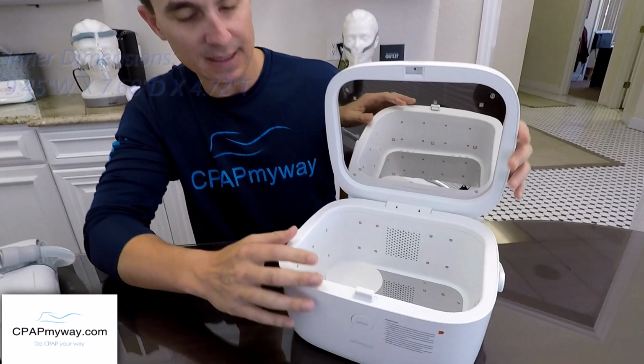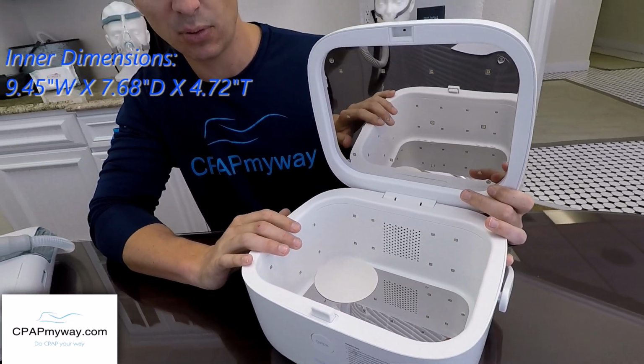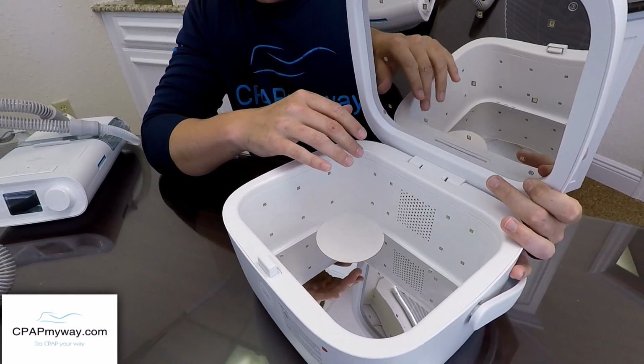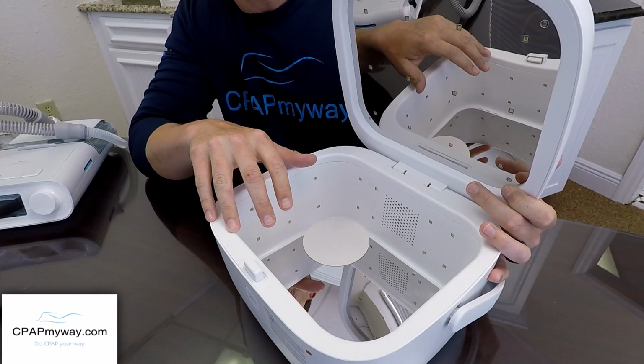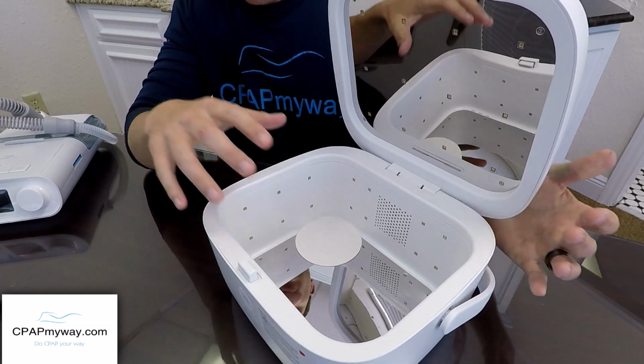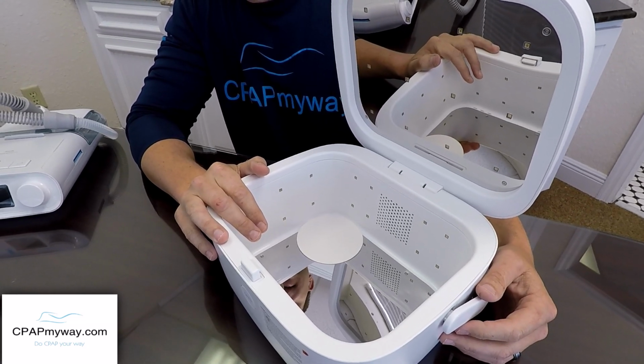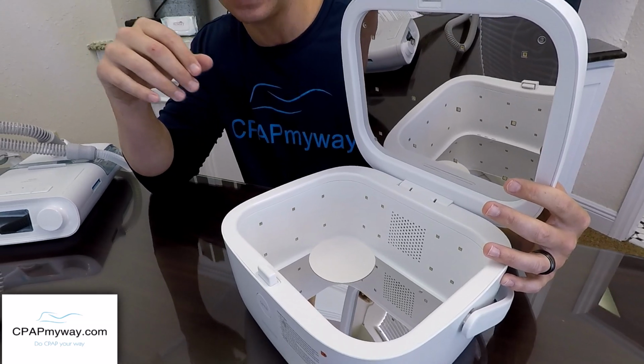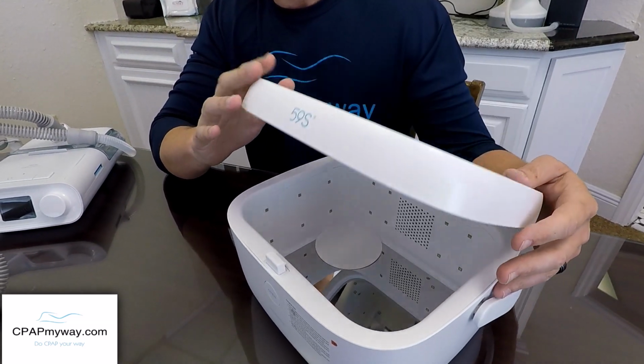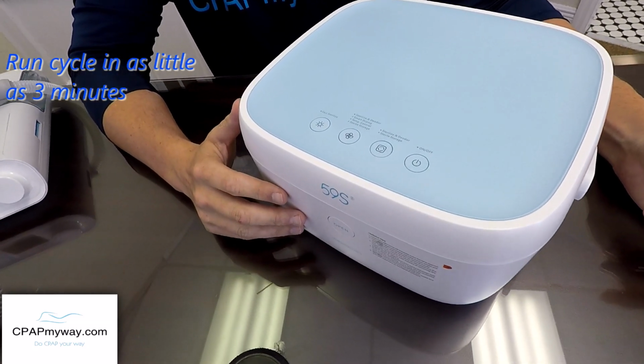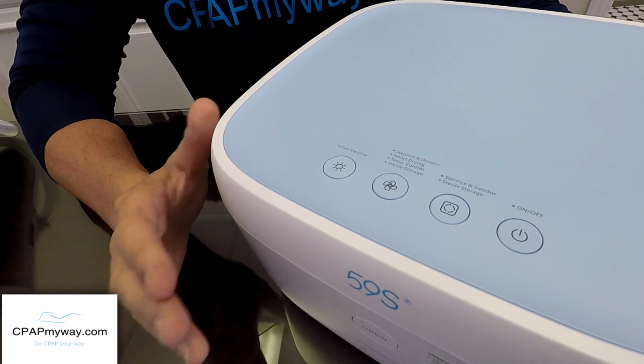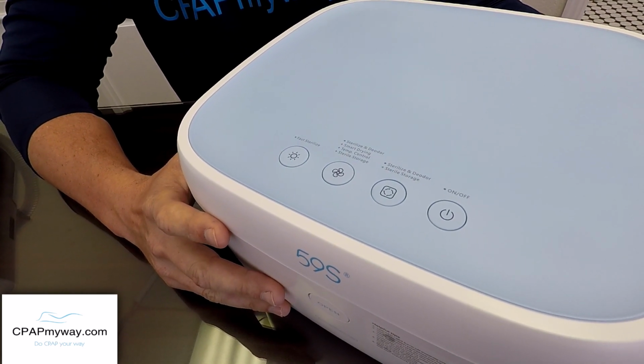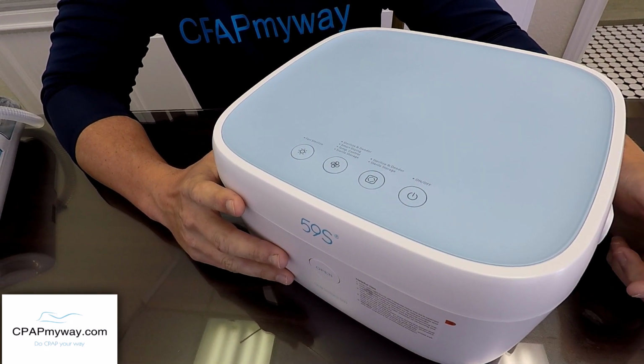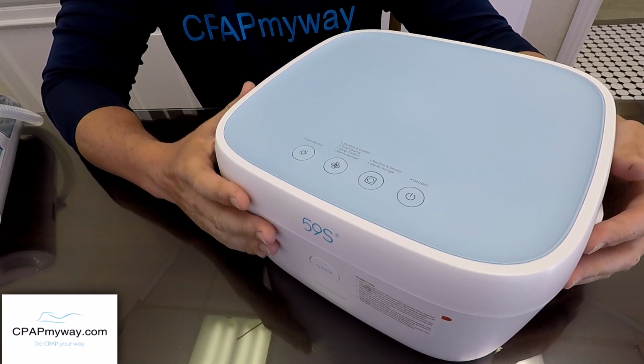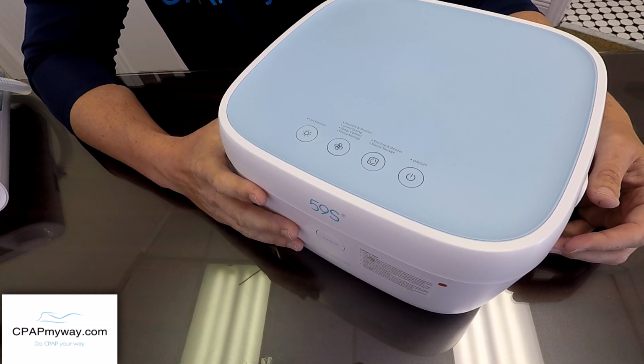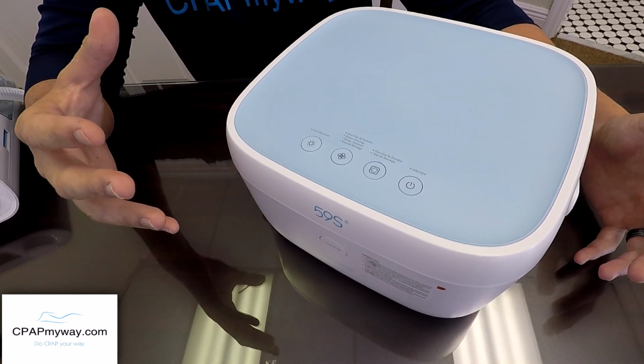Inside the device itself is the largest UV capacity, so it's 9.45 inches by about 7.68 inches, by 4.72 inches deep. So it holds quite a bit, and it definitely is something you'll want to consider because this has some options as far as what you'll be putting in there. This particular device has a couple of runtime options. There's one as quick as just a 3-minute option that will do a quick UV sterilization on anything you put in there. But it's also got a dry mode and storage mode, which has the built-in humidity sensor that will tell it if your equipment's dried out enough or not. And so sometimes that'll take a little bit longer. It'll run until it's done, basically.